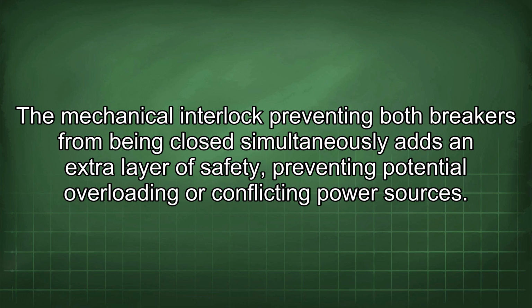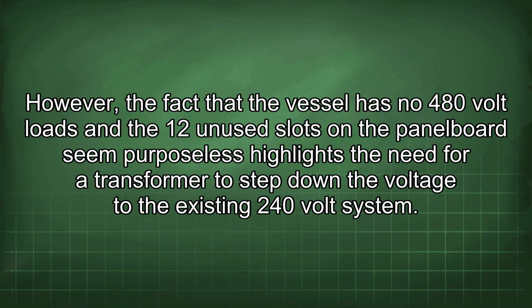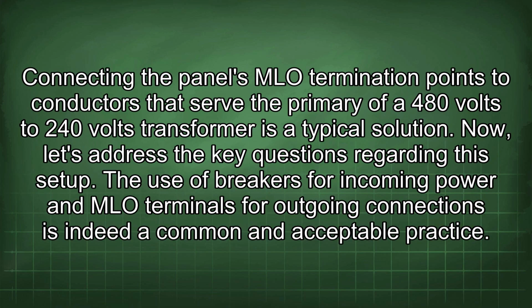conflicting power sources. However, the fact that the vessel has no 480-volt loads and the 12 unused slots in the panel board seem purposeless highlights the need for a transformer to step down the voltage to the existing 240-volt system. Connecting the panel's MLO termination points to conductors that serve the primary of a 480 volts to 240 volts transformer is a typical solution. Now, let's address the key questions regarding this setup.